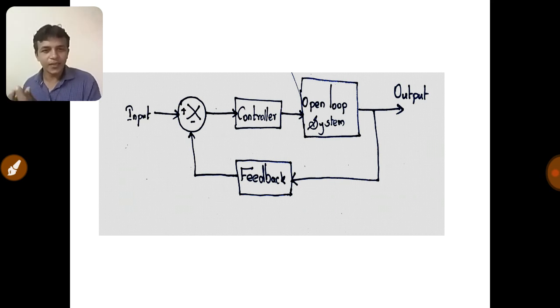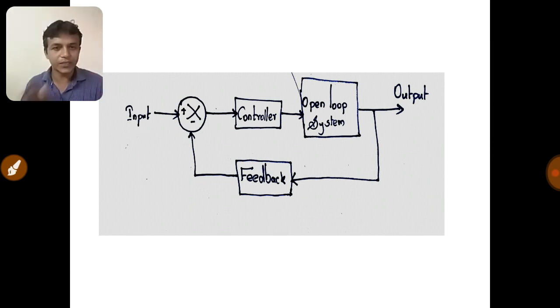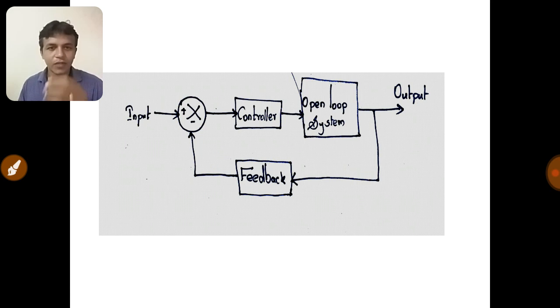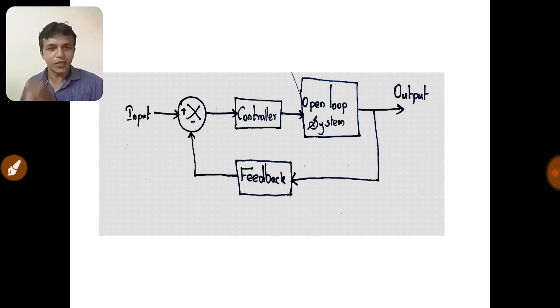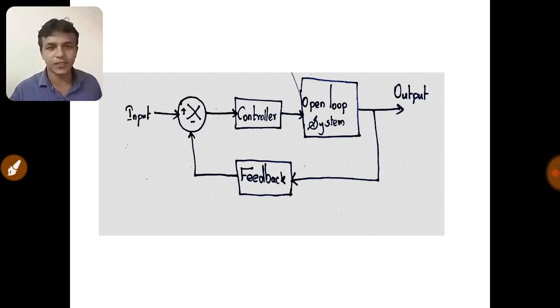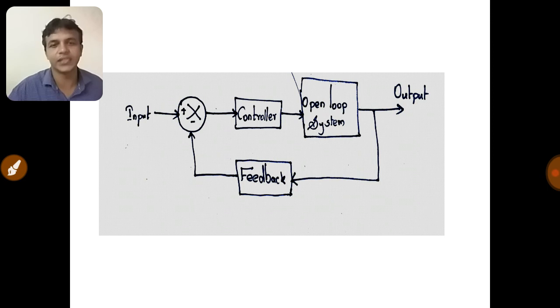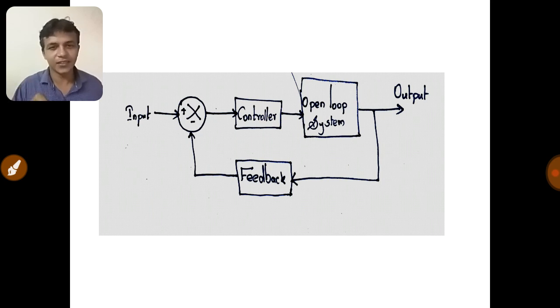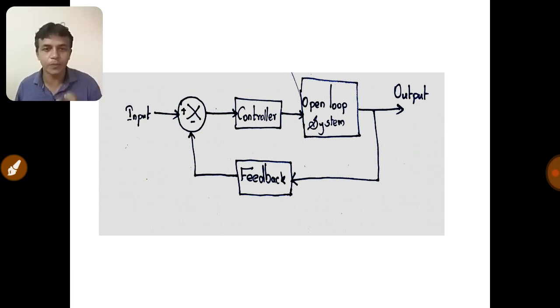The temperature sensor sends feedback by converting the chillness — in the form of temperature — into a voltage signal. That signal is sent back and, on receiving it at the input stage, the controller controls the switching of the compressor. Here there is no dependency on time; the entire system depends on the output condition required, which is chillness. If chillness is not there, the compressor runs; if chillness is maintained, the compressor is switched off.